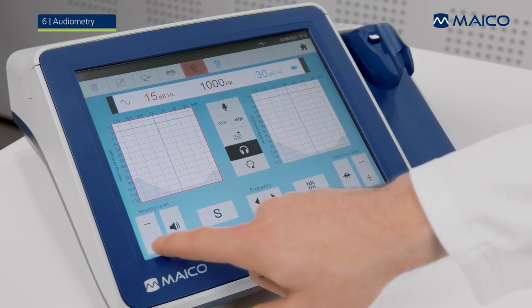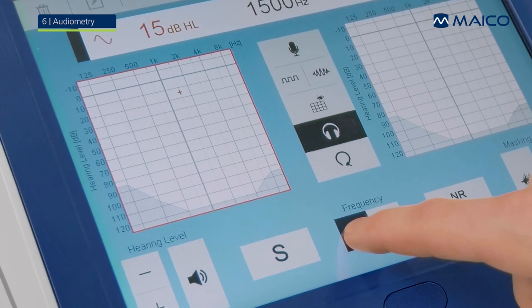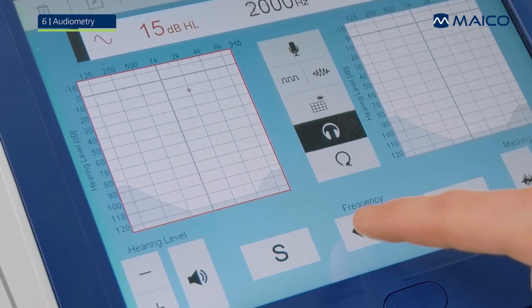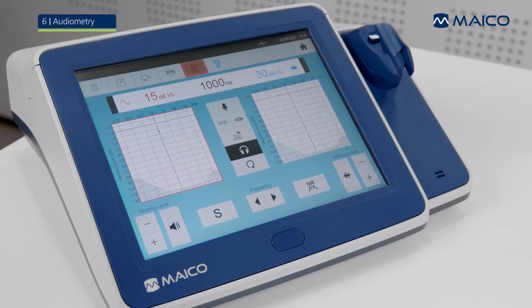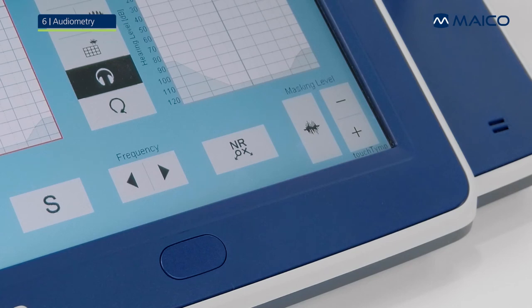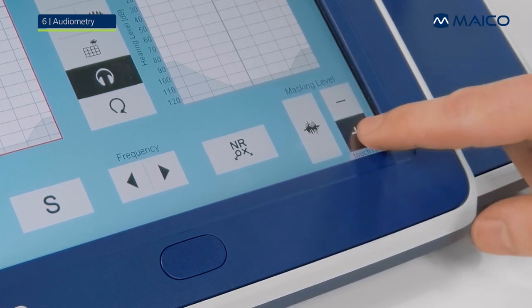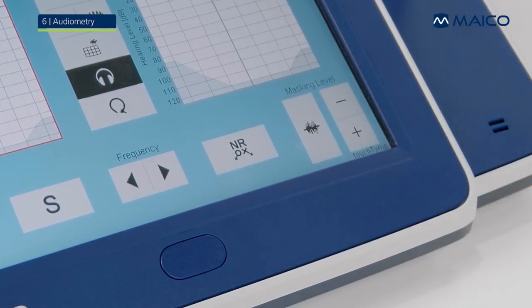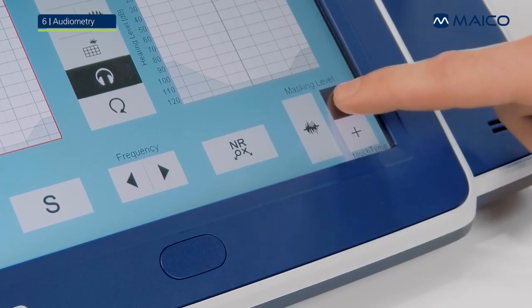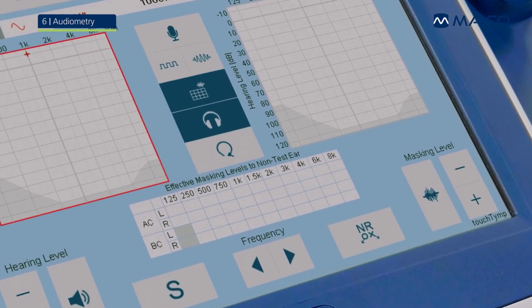With the hearing level buttons, you adjust the stimulus level, whereas with the frequency buttons, you adjust the presented frequency. Use the store button to record the hearing threshold at the current level and frequency. The no response button allows you to store that no hearing threshold could be recorded. If masking is required, the masking levels can be adjusted with the level buttons. The masking noise is permanently presented to the patient by pressing the masking button. The effective masking levels are shown in the masking table.